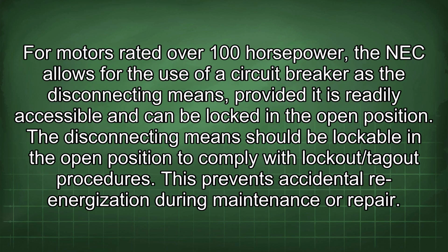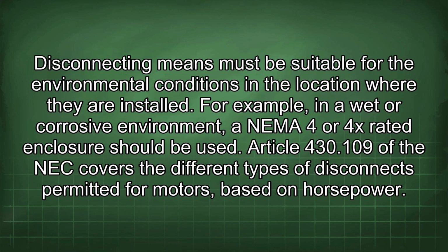For motors rated over 100 horsepower, the NEC allows for the use of a circuit breaker as the disconnecting means, provided it is readily accessible and can be locked in the open position. The disconnecting means should be lockable in the open position to comply with lockout/tagout procedures. This prevents accidental re-energization during maintenance or repair. Disconnecting means must be suitable for the environmental conditions in the location where they are installed. For example, in a wet or corrosive environment, a NEMA-rated enclosure should be used.